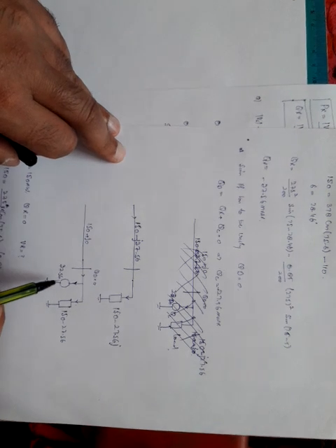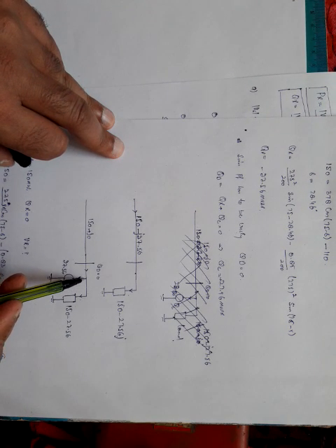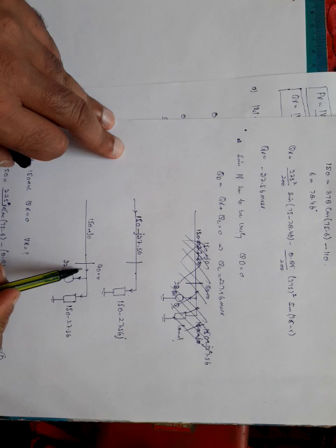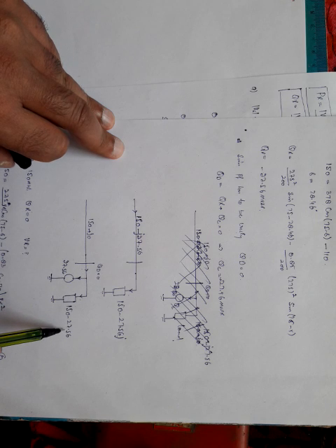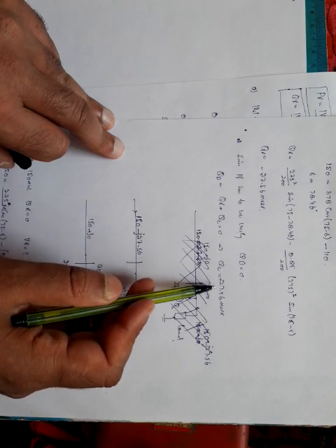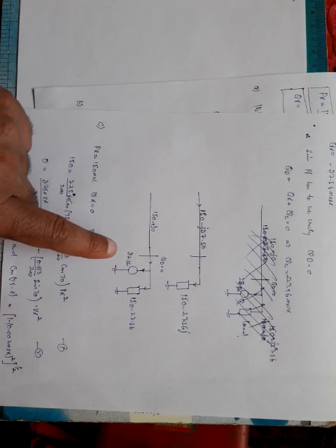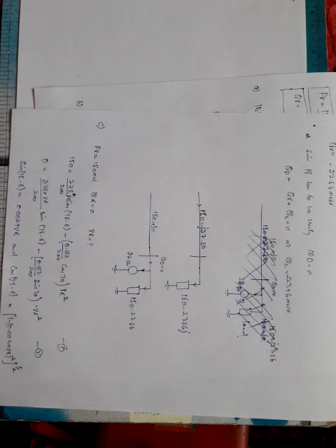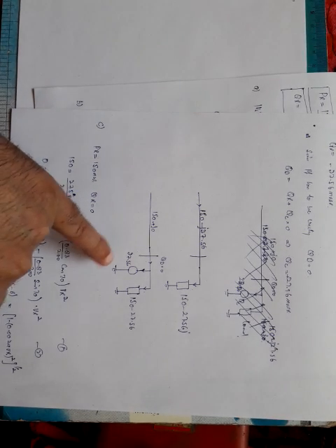Or you can get it from here also, since QD should be equal to 0, by simply using the KCL over here, this QD should be 0, and it is equal to QR plus QC, that is equal to 0. From this we can calculate QC is equal to plus 27.56 MVAR.